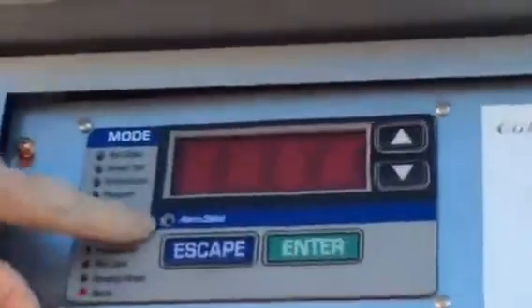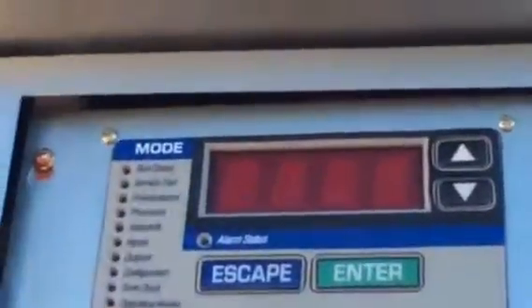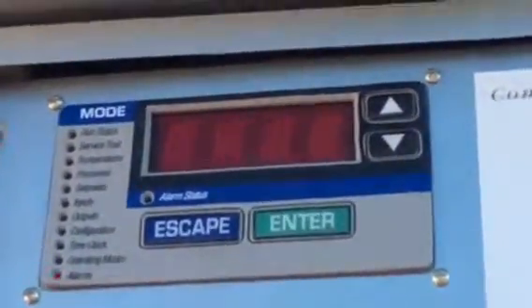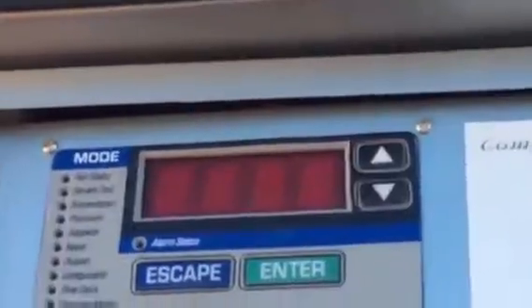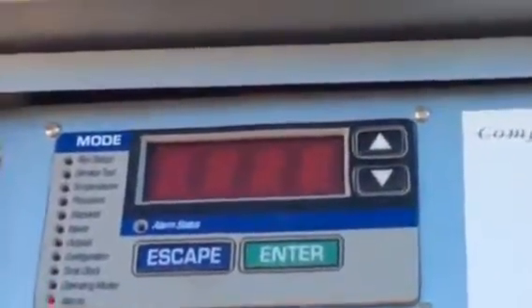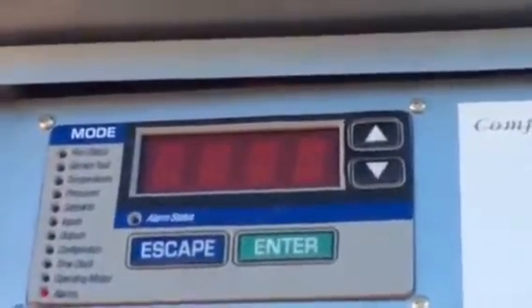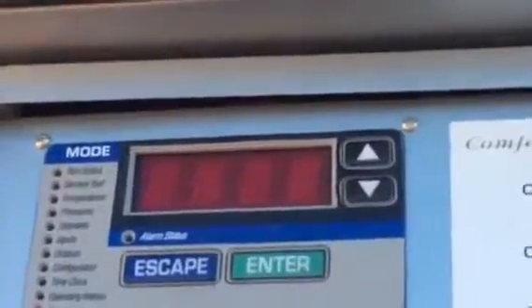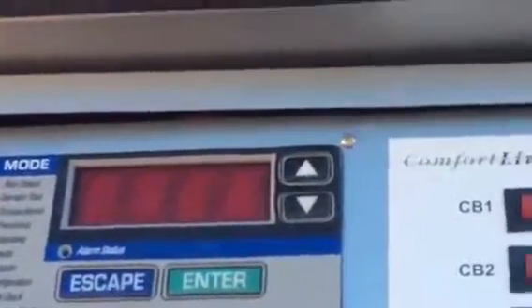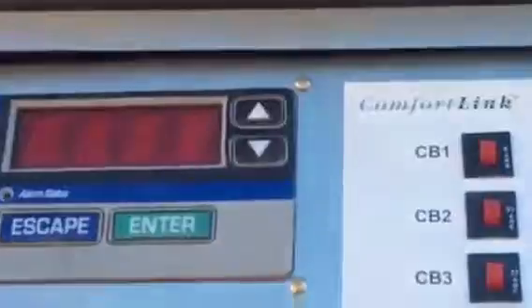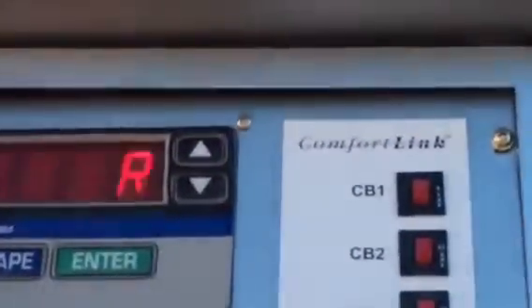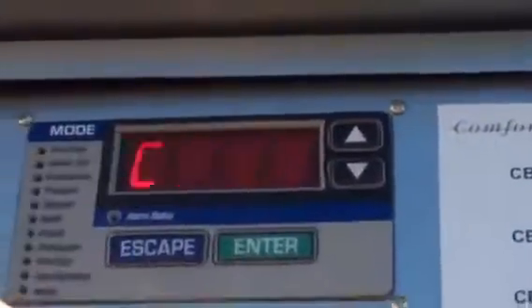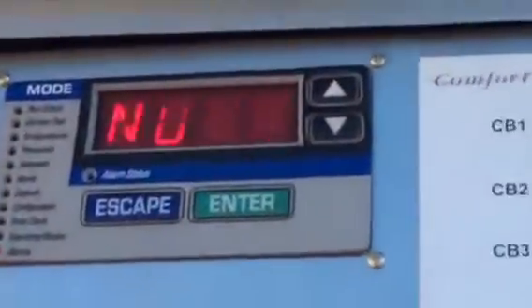So operating modes are in there, and alarms is a big one. There's a separate LED light that says alarm status. That's blinking. It means there's been an alert. One of the ones that are typically retry. On solid is there an alarm, something that critical happened and it'll shut down. So right now we have nothing. So it alarms, current, alarms, there's none.